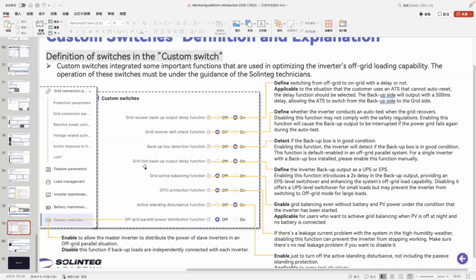And the next is the grid loss backup output delay function. This defines the inverter's backup output time as a UPS or as an EPS. UPS means that the switch time between on-grid and off-grid is very quick. EPS level switch time is a little bit longer than UPS, but is still finished very quickly. If we choose to enable this function, we can set the inverter's backup output as EPS, which adds a 2-second delay in the backup output. So, for example, if there are some large loads in off-grid mode, it helps them switch more smoothly during daily operation.